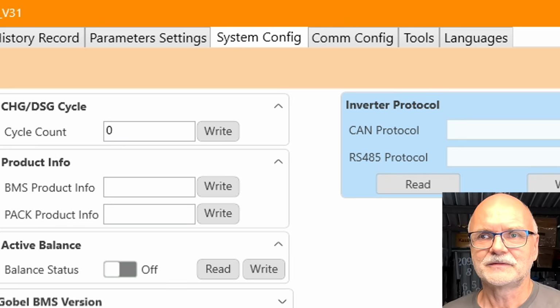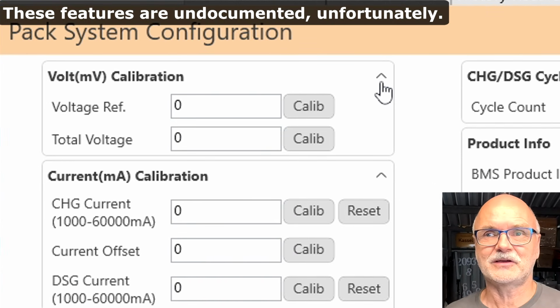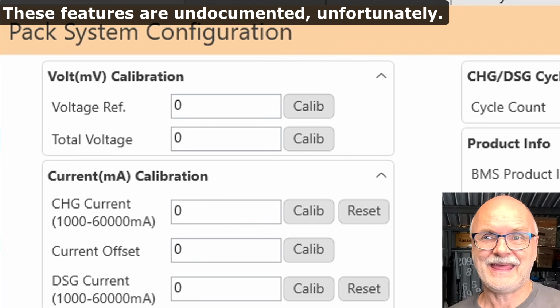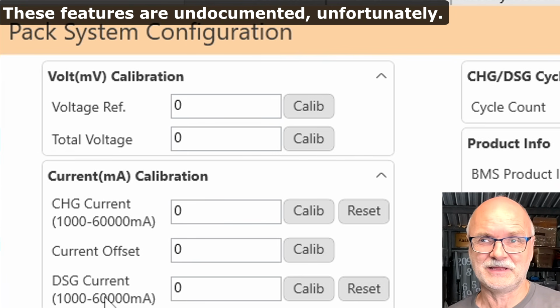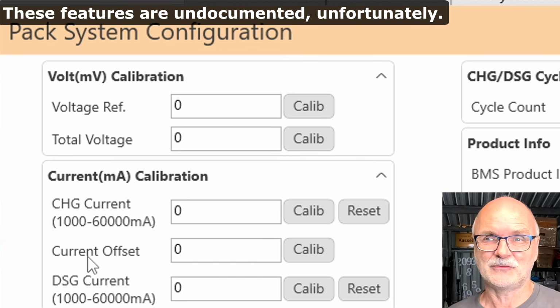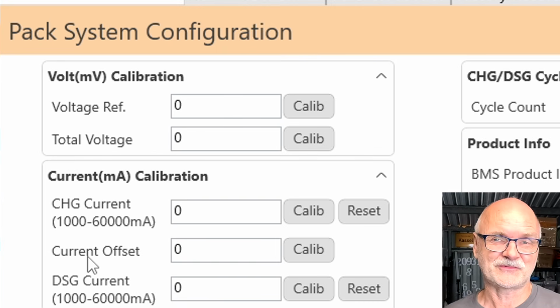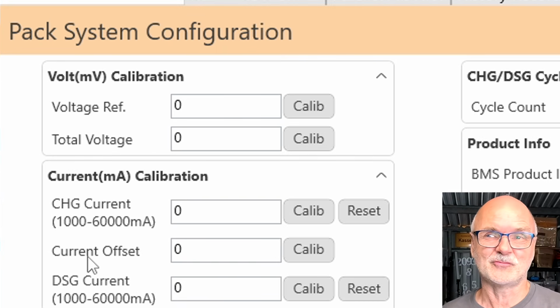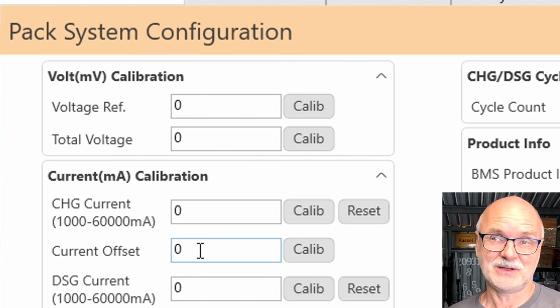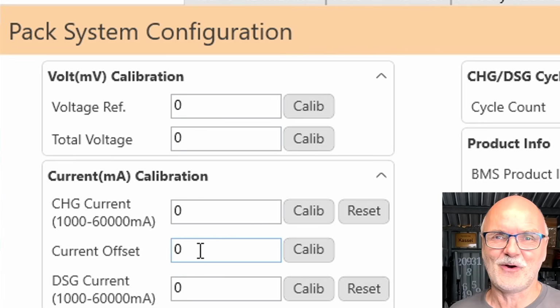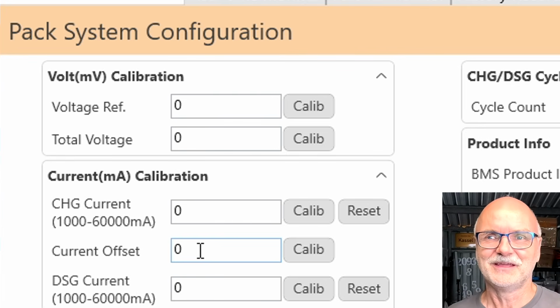System config, this is very interesting. We can actually calibrate the voltage, calibrate the charge current and the discharge current separately, and we also have a current offset. So if your BMS constantly shows 1 or 2 amps too much, you can offset this with these parameters.